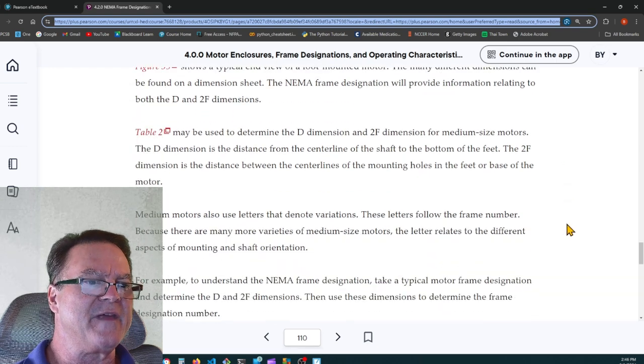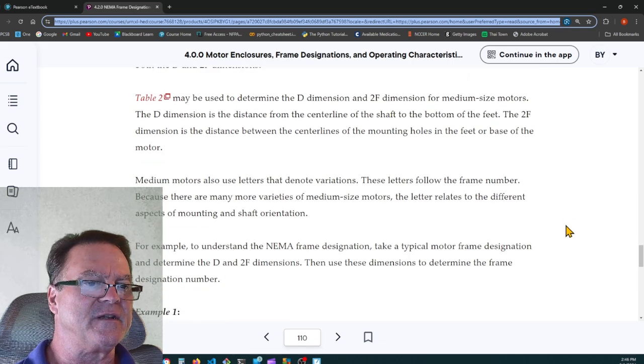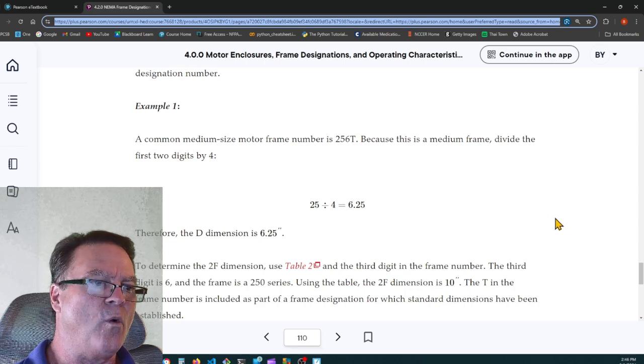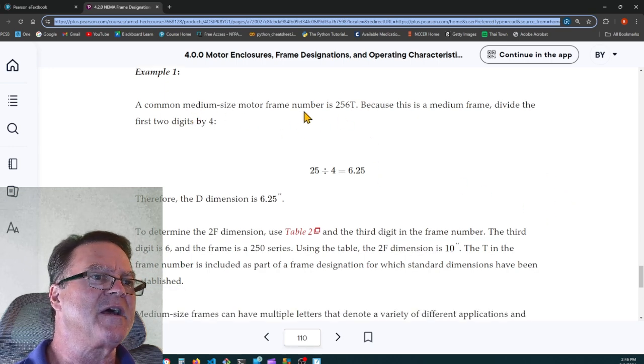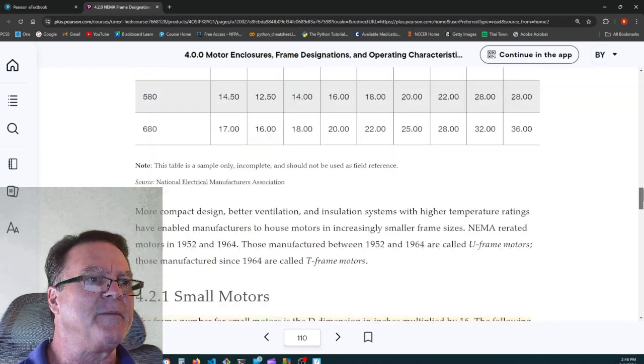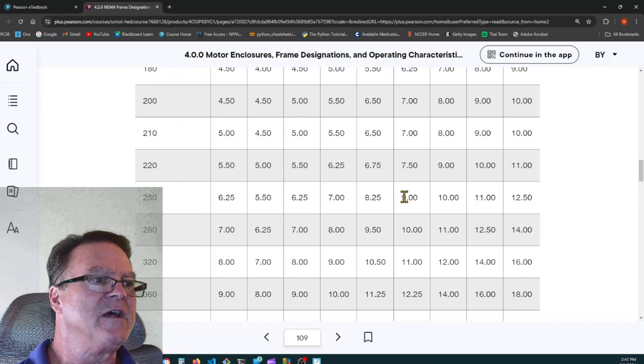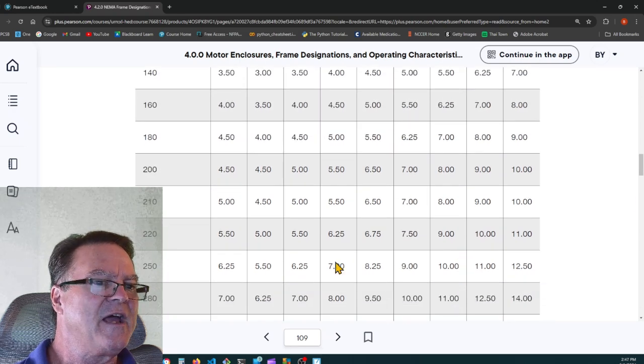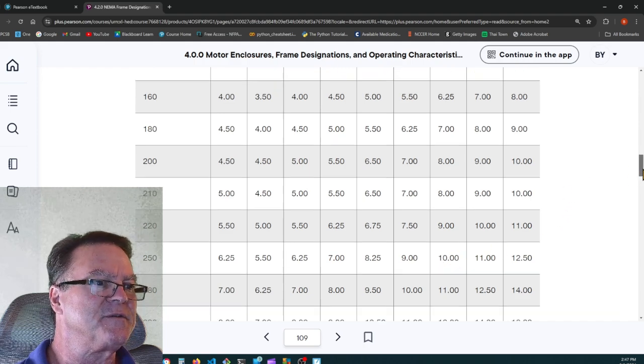So the first two digits will be that D dimension. And again, it's the D dimension times 4. So common medium-sized motor frame number is 256. So the first two digits is 25. If you divide that by 4, it's 6 1/4 inches. And it's in the 250 range. So if we look at the third digit, 6, we can see on that frame, here's the 250, and here's 6. 6 on the 250 frame is 10 inches. So the D dimension is 6 1/4 inches, and that 2F dimension between the bolt holes is 10 inches. That's what they're saying.